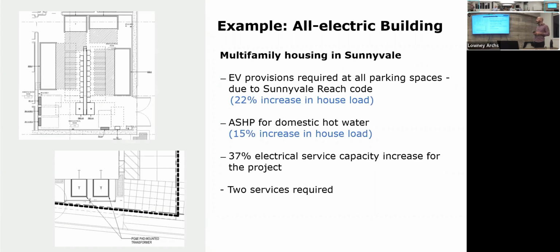And because of that, we saw a 22% increase in the load for the building because of the EV charging requirement. The air source heat pumps for domestic hot water heating also had an impact, a 15% increase in the load compared to a gas water heater. So overall, there was a 37% electrical service capacity increase for that project. And because of that, 2 services were required. So yeah, you will see the impact.